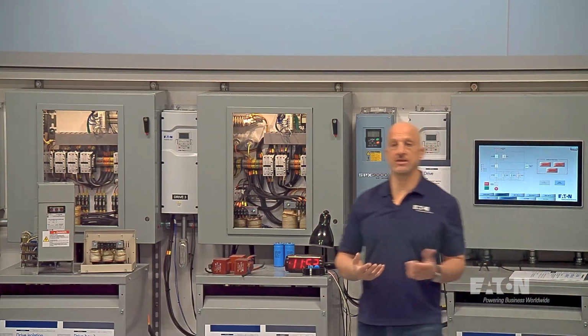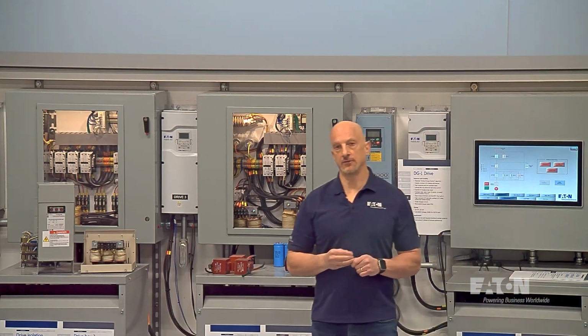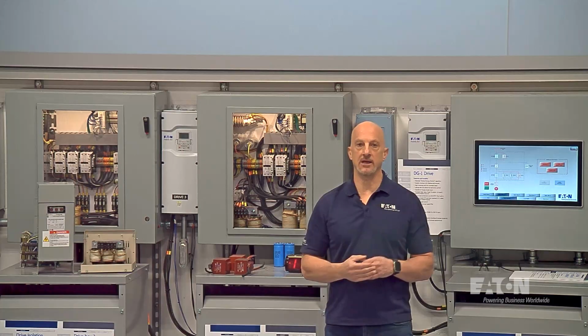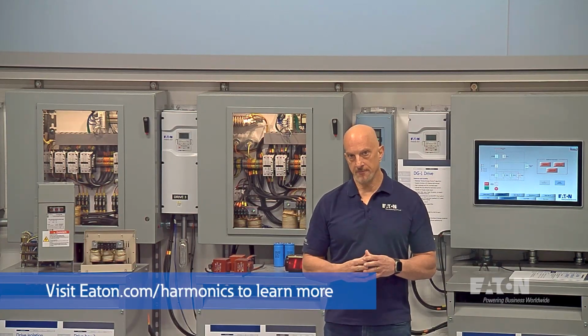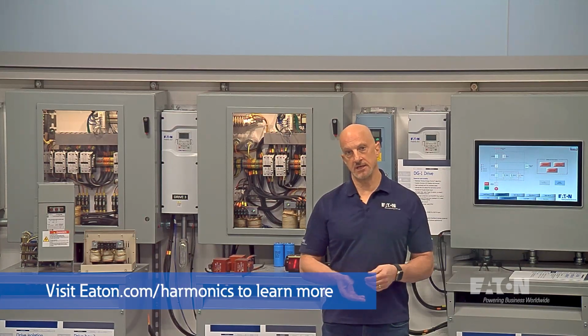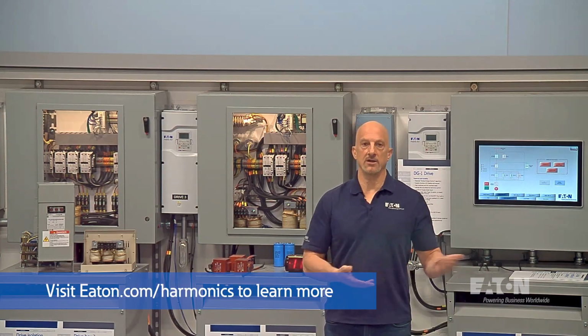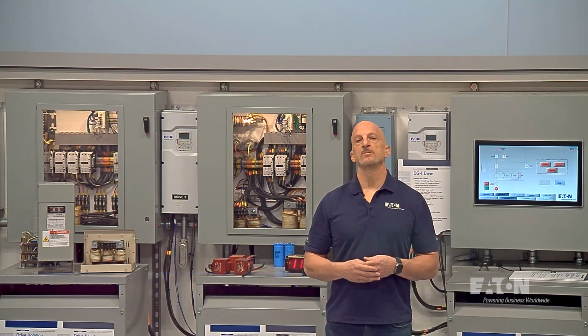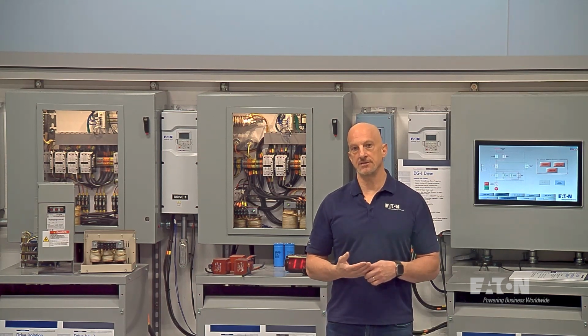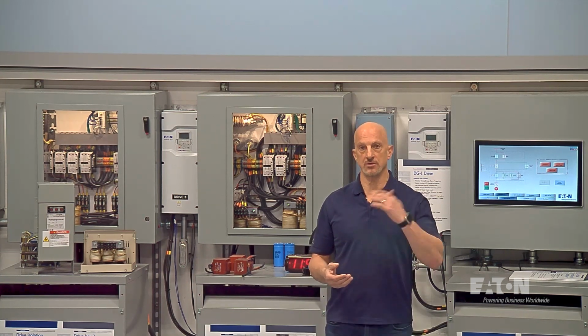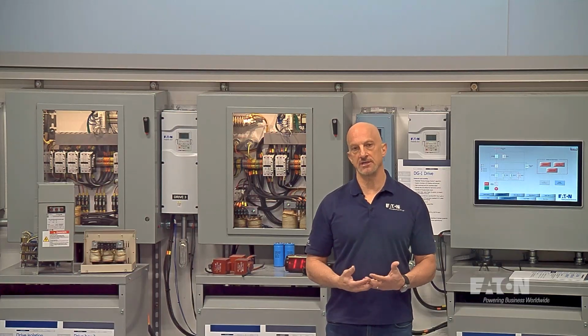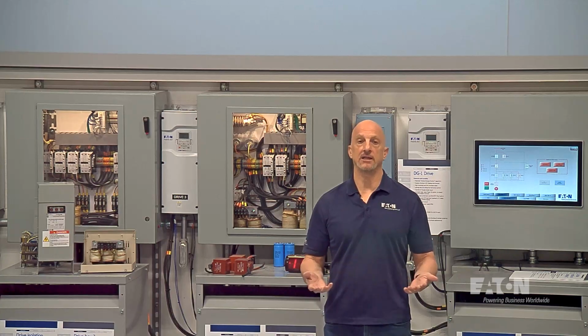So again, pretty common question that we get regarding active filters. Why do I need a line reactor? You need a line reactor to stabilize that current going into the drive so that the active filter doesn't increase it by shorting out essentially the source impedance. And then why does the current increase? Just for that reason, because we're shorting out the source impedance, which essentially is constricting the flow like a line reactor normally would do.